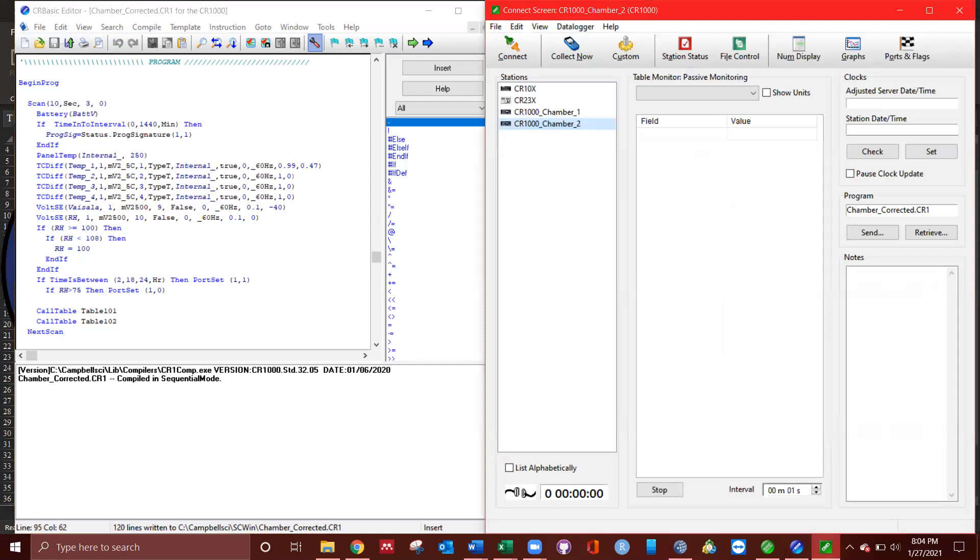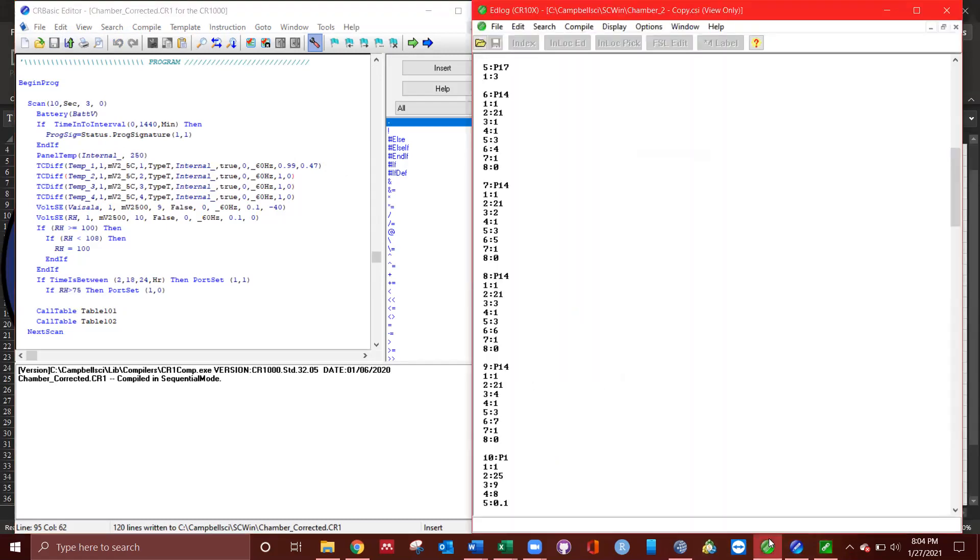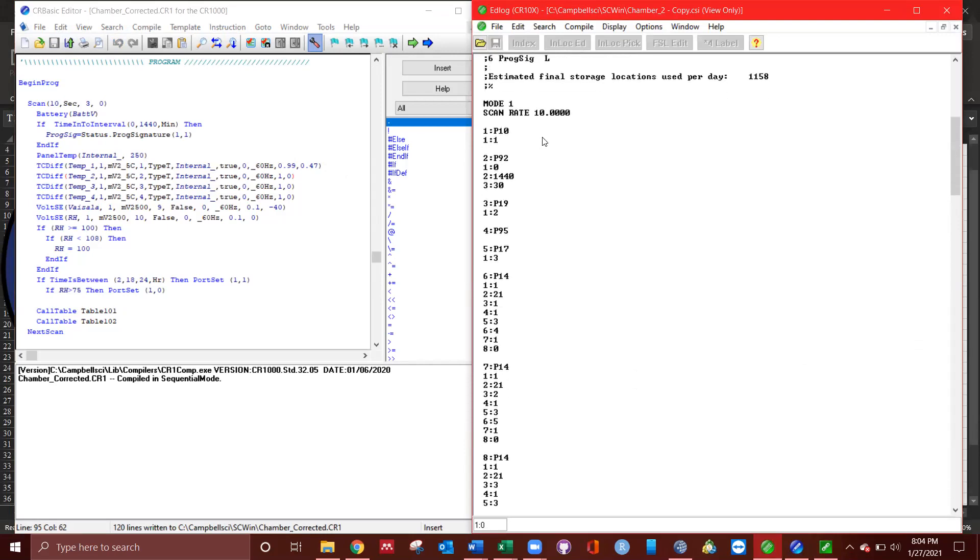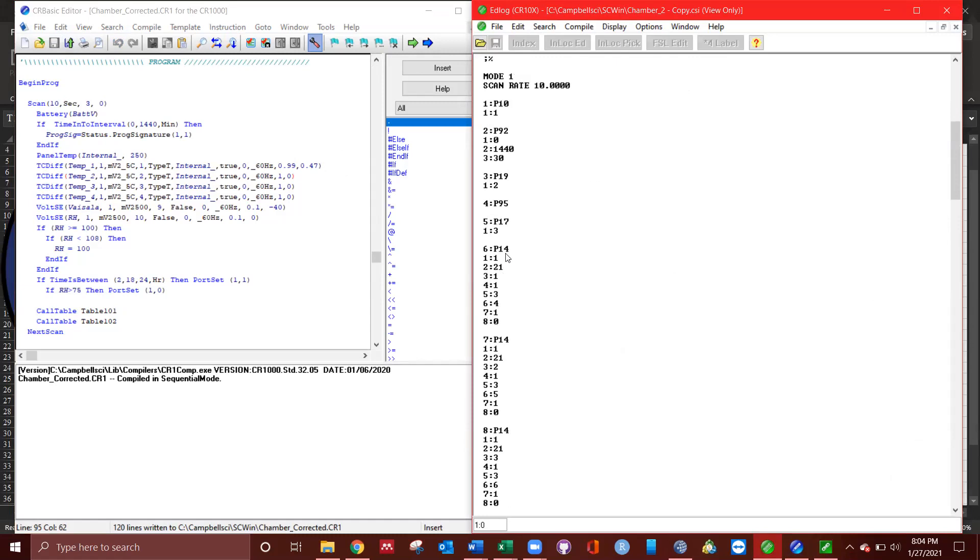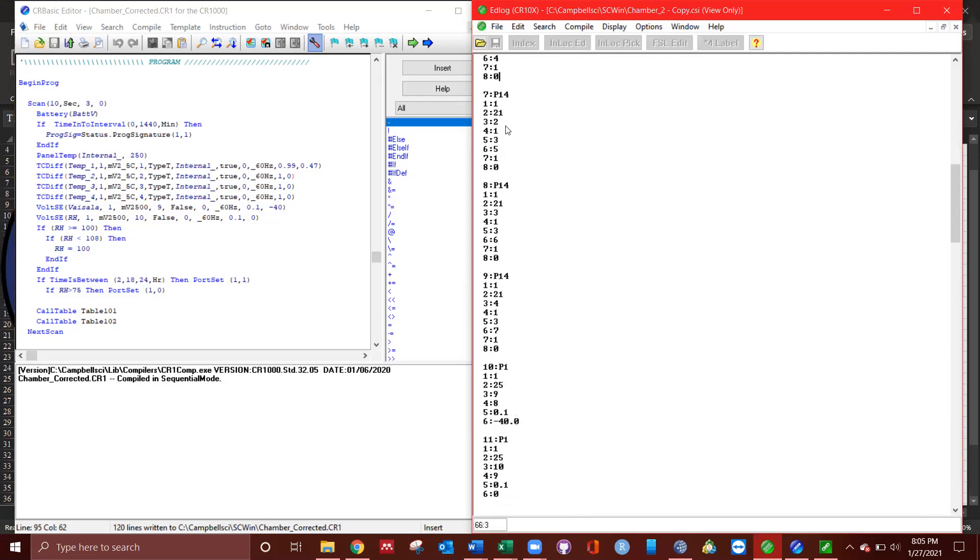If I want to do this in the ed log for the CR10X, the same thing. Right here, you need to figure out where the first thermocouple is. In this case, P14 is my first thermocouple 7, 1. This 1 is our M and the 0 is our B. This is just read only, but basically I would delete here and write in my 0.99 M, and then I would delete here and put in my 0.47 B. In that case, you just hit compile and save, and that'll be your new program file. I'll do this for 1, 2, 3, 4 thermocouples.